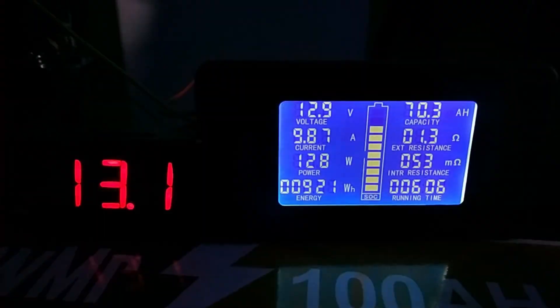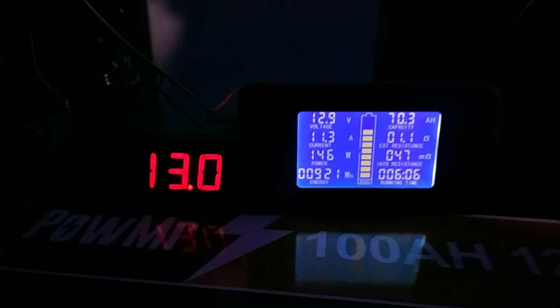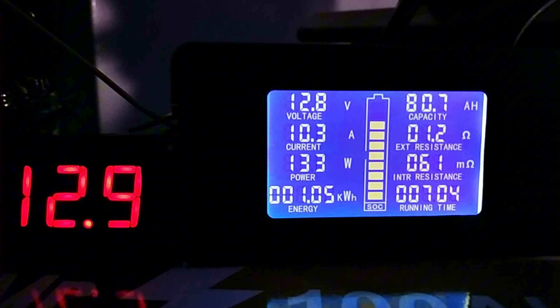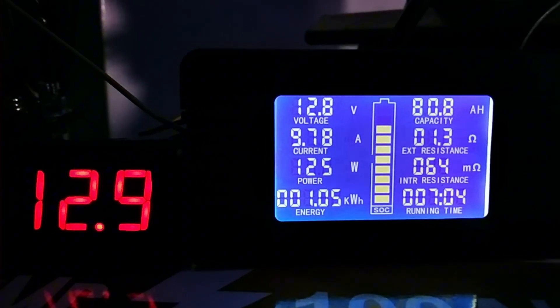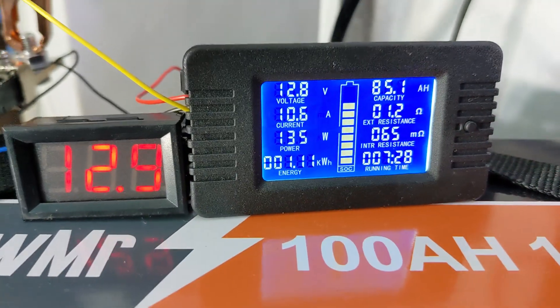After six hours, we have used 70 amp hours and the battery is still showing a good voltage of 12.9 volts. After seven hours, we have used 80 amp hours, which is the recommended depth of discharge. However, this is not the goal of the video — we are going to do a full capacity test. After seven hours 30 minutes, we have reached the nominal voltage of 12.8 volts and used 85 amp hours.